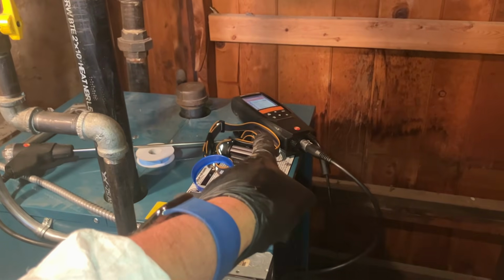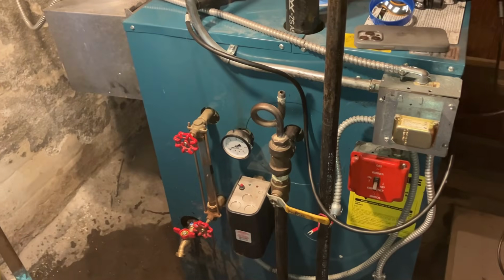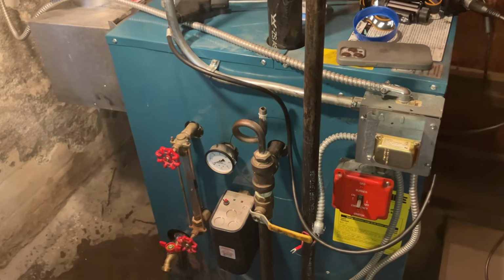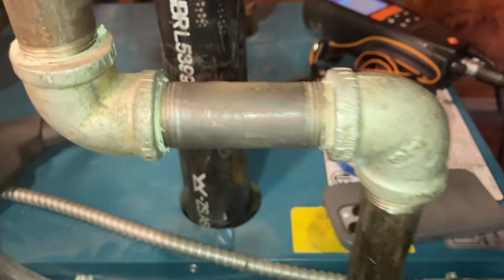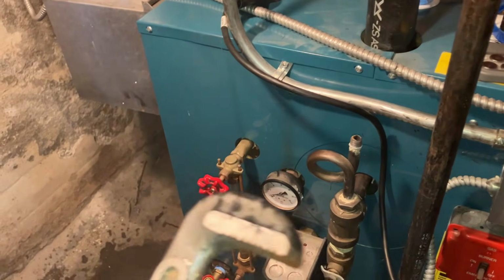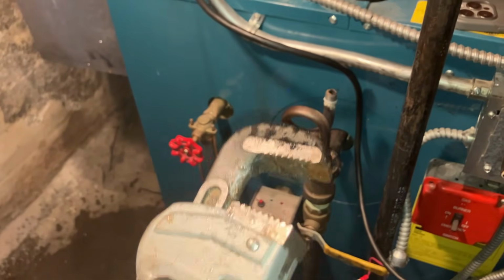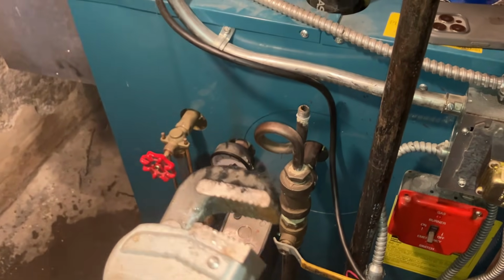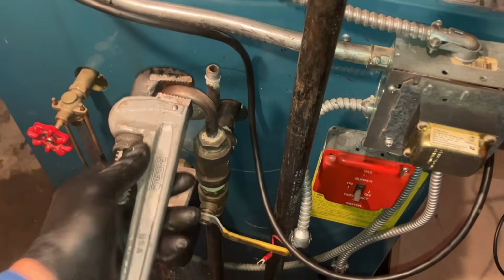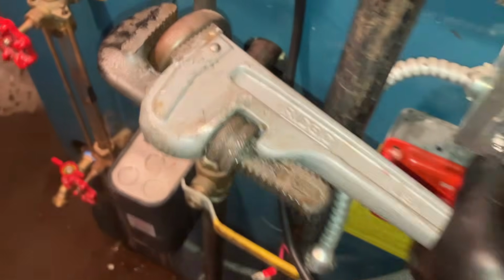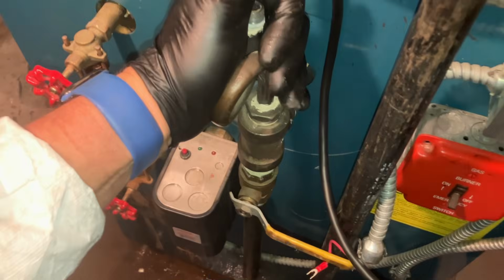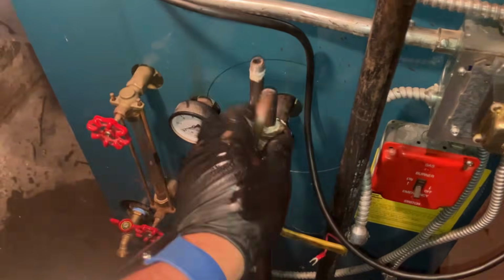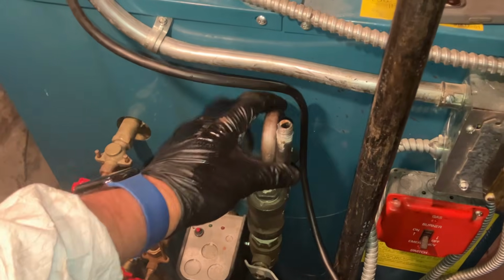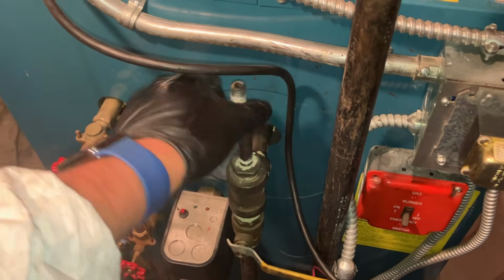I got my Testo combustion analyzer plugged in. Had a low battery, so now she's charging. We're gonna fire this up once we check the pigtail out. Make sure that's clean, so let's just quickly check this. I always do it the wrong way. You guys have that same problem too? Guaranteed it's clogged. Guaranteed. This is a black steel pigtail. She's definitely clogged.